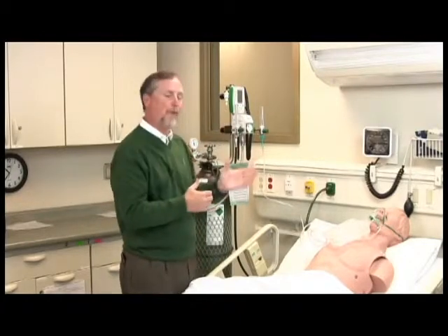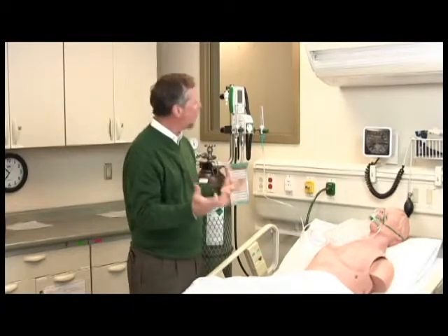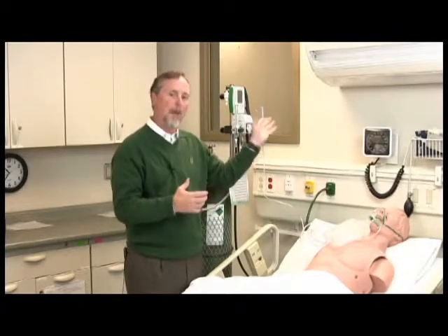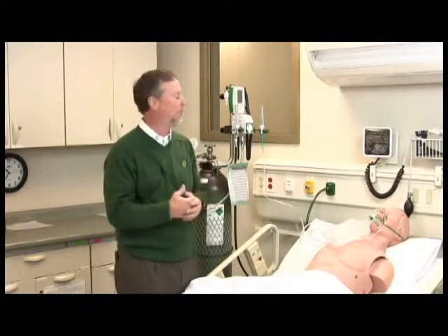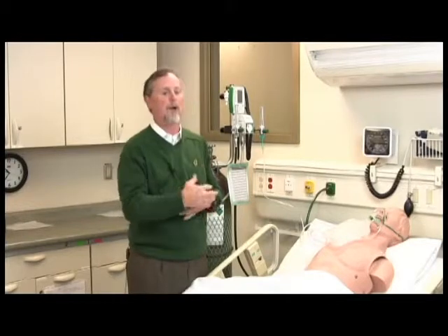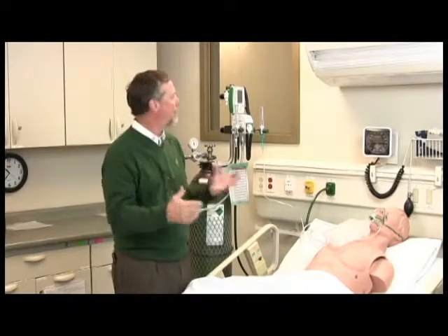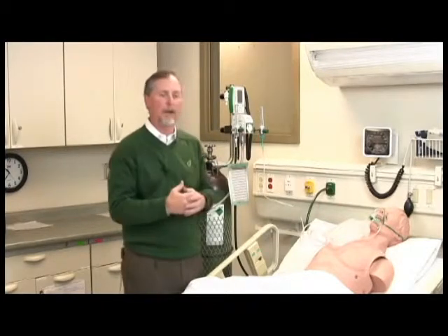We use oxygen flow meters. We don't have specific Heliox flow meters with this because at every different level of Heliox, you would come up with a different calculation of what the flow is. So it's a little bit hard to come up with a Thorpe tube style flow meter to cover all the concentrations of Heliox. That would really require some kind of electronic flow meter with feedback into the blender.